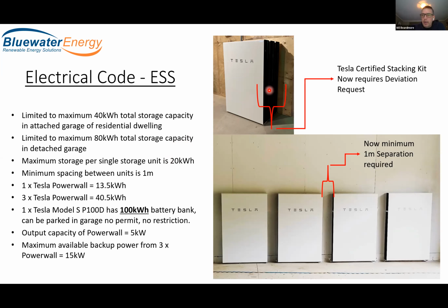So we've been in discussions with ESA and CSA, which is actually where this rule came from, and we just recently had a ruling that in Ontario we're going to be allowed to do this with a deviation request. That means it's an extra step and more time in the project. We submit a deviation request to the electrical authority, and we request permission ahead of time to be able to stack the units.